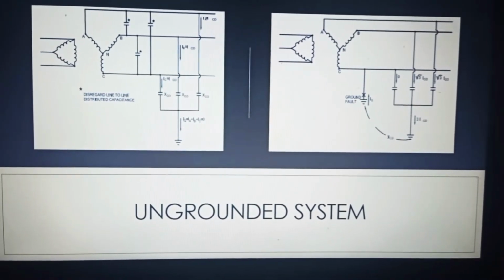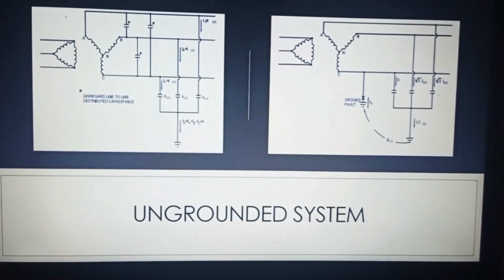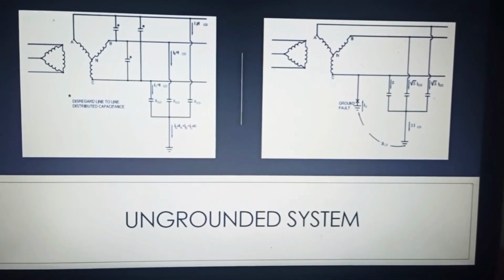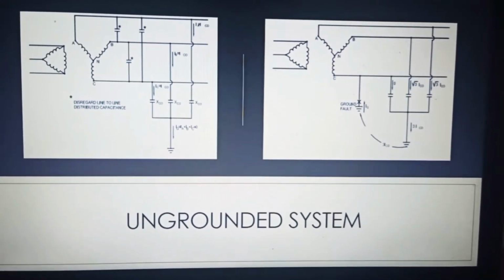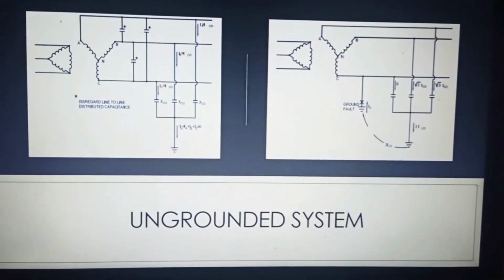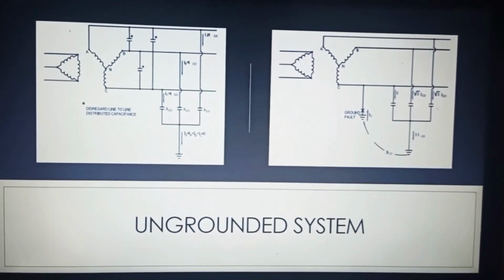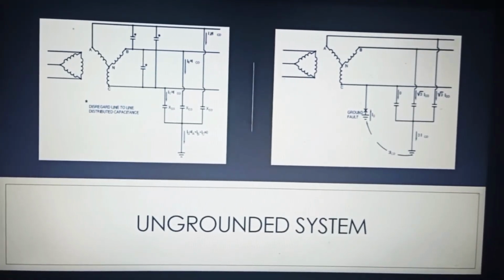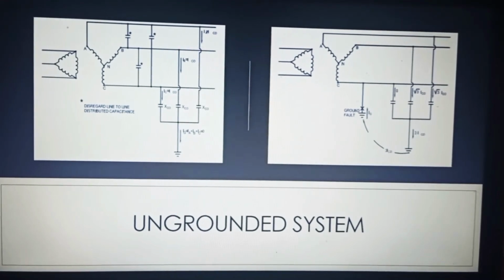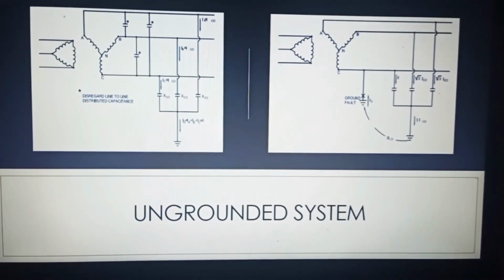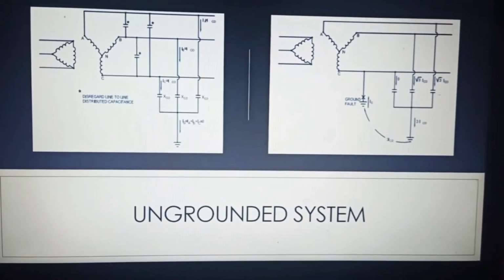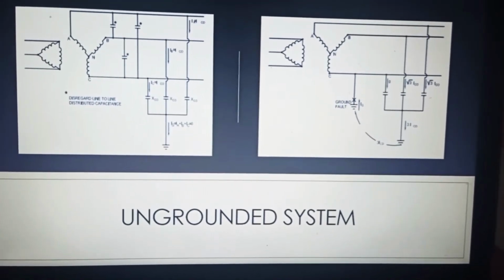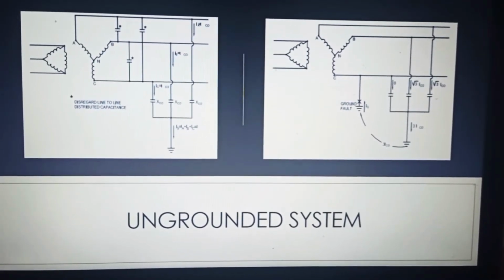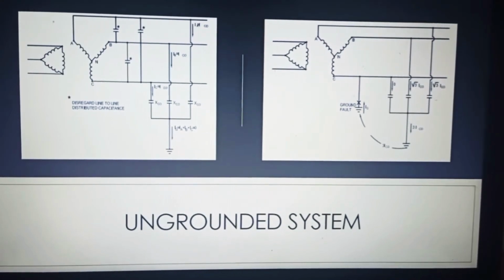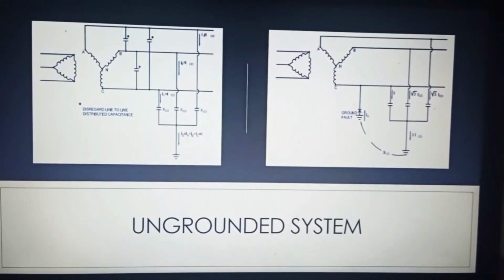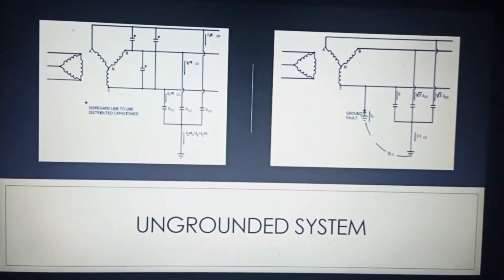If one of the system conductors, phase C for example, faults to ground, current flow through the capacitance to ground will cease, since no potential difference across it now exists. The voltage across the remaining two distributed capacitors will, however, increase from line to neutral to line to line. The capacitive charging current in the two unfaulted phases will therefore increase by the square root of 3, as shown in picture number 2. The line ground currents are no longer 120 degrees, but 60 degrees apart. Hence, the vectorial sum of the capacitive charging currents to ground is no longer 0, but 3 times the original charging current per phase.